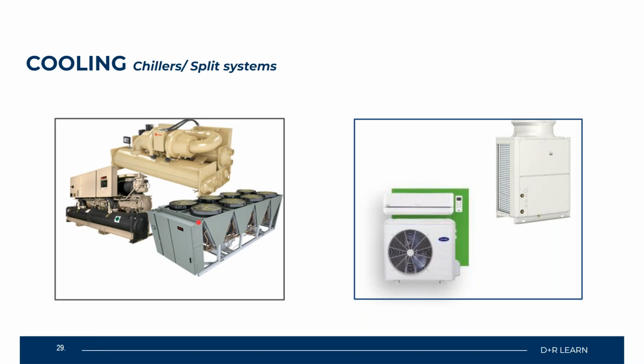Now once again, your chiller is going to supply chilled water to your cooling coil in your air handler system. But the chiller itself is really good at supplying cooling for IT server spaces. A great example of that is chiller rack systems, where you have chilled water directly pumped into cooling coils within the rack systems where servers are located. Very complex and expensive system to integrate into your IT operation, but it will be able to handle the BTUs emitted by rejecting that heat load out to the ambient air.